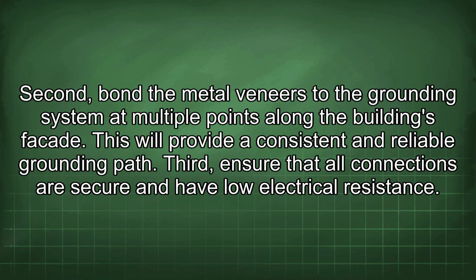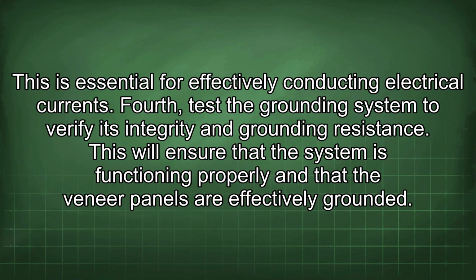Second, bond the metal veneers to the grounding system at multiple points along the building's facade. This will provide a consistent and reliable grounding path. Third, ensure that all connections are secure and have low electrical resistance. This is essential for effectively conducting electrical currents. Fourth, test the grounding system to verify its integrity and grounding resistance. This will ensure that the system is functioning properly and that the veneer panels are effectively grounded.